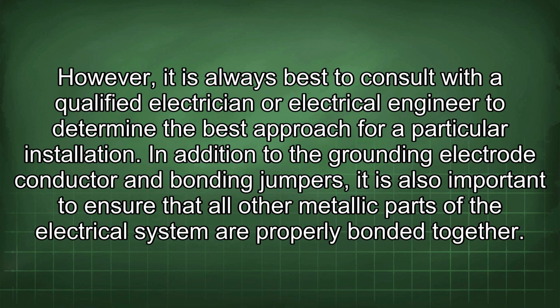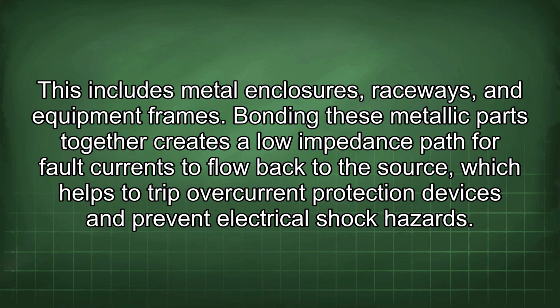In addition to the grounding electrode conductor and bonding jumpers, it is also important to ensure that all other metallic parts of the electrical system are properly bonded together. This includes metal enclosures, raceways, and equipment frames. Bonding these metallic parts together creates a low impedance path for fault currents to flow back to the source, which helps to trip overcurrent protection devices and prevent electrical shock hazards.